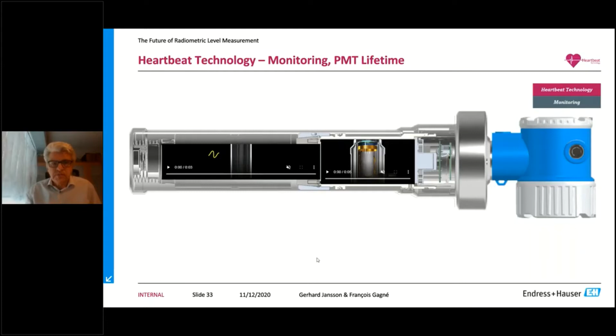So that's the photomultiplier, gamma radiation, and that is the high voltage that I was talking about before. The high voltage is a very important part of the detector, because through it we regulate the voltage, and it will also compensate for very high or low temperature, and also aging of this scintillator material. So we run typically at a low value, and eventually over time you are going to get to higher and higher values, and when you exceed 1200 volt, the detector is probably gone and needs to be replaced.